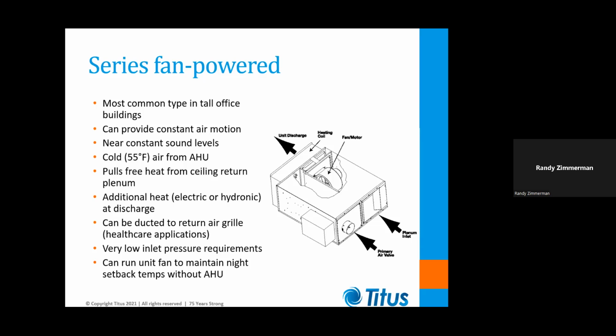And that's important to note, because if the blower in this series fan-powered unit is not running, there's no way to move primary air to the room. If the blower is not running, it's almost impossible to blow primary air through the pressure drop created by that dead blower. So what will happen is the primary air will simply follow the path of least resistance and do a U-turn and head right out the induction port.